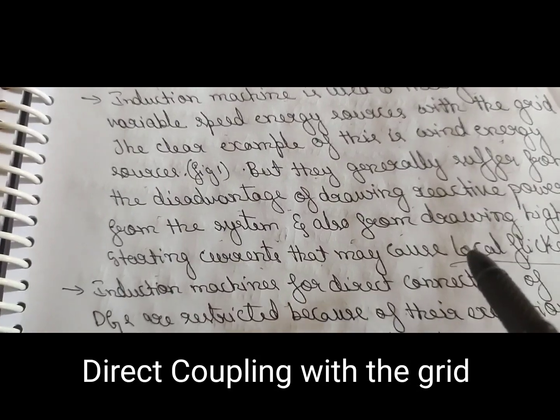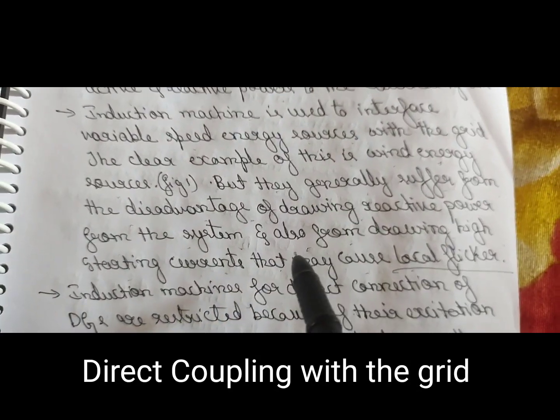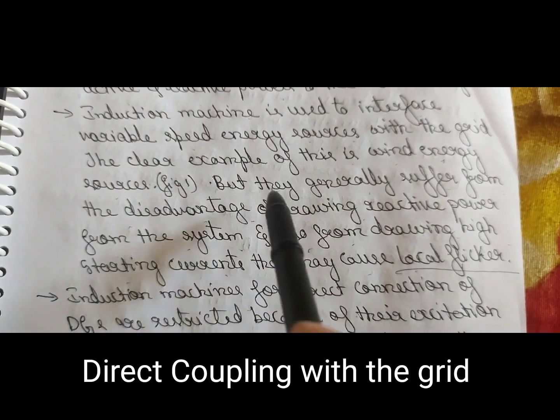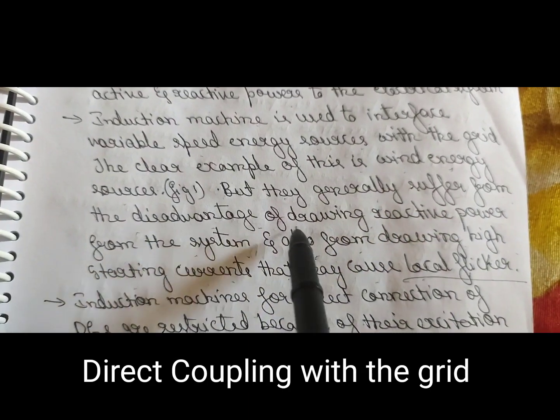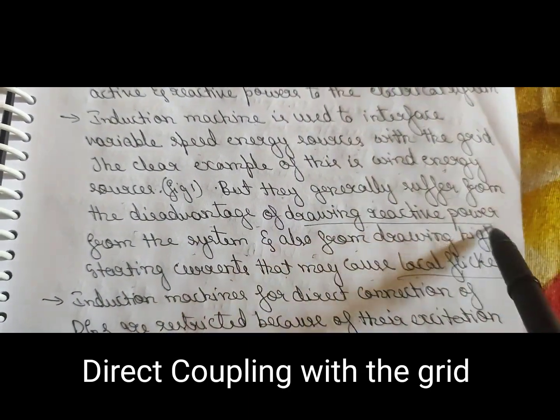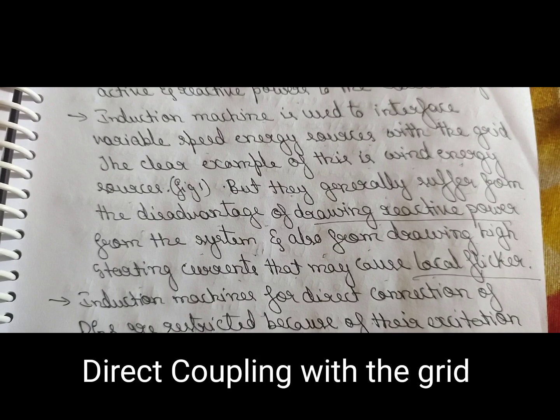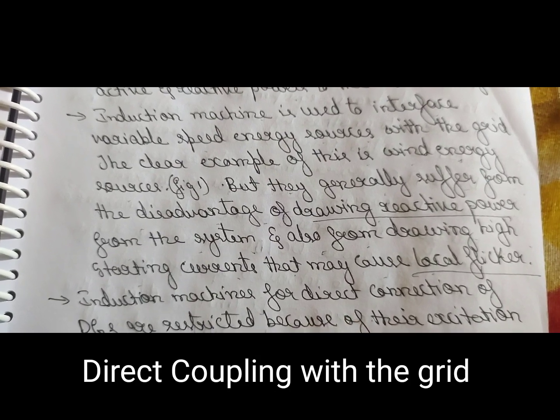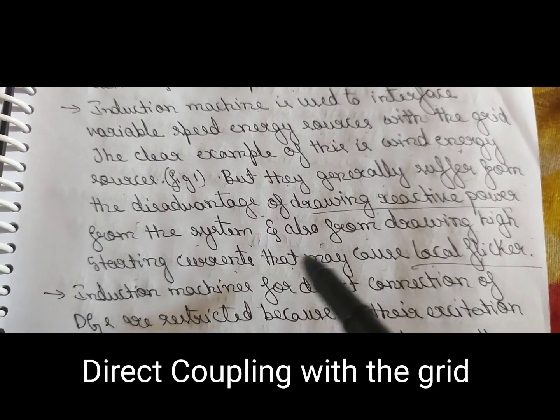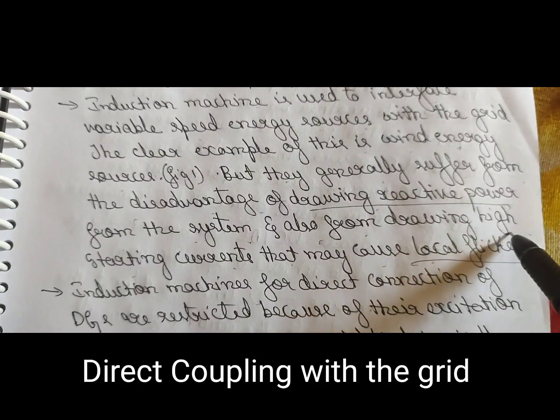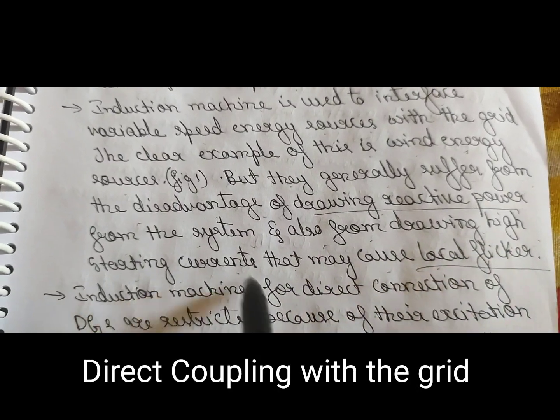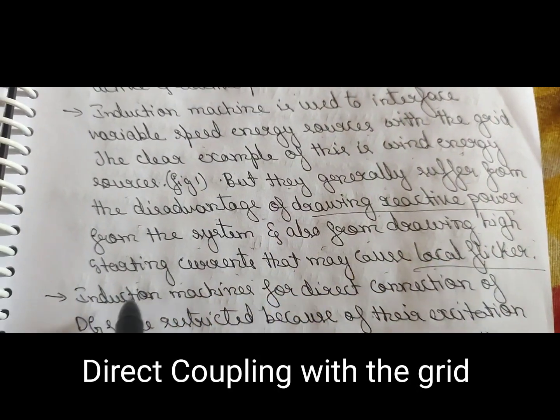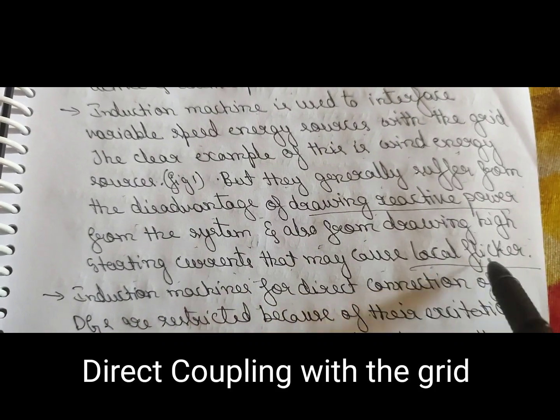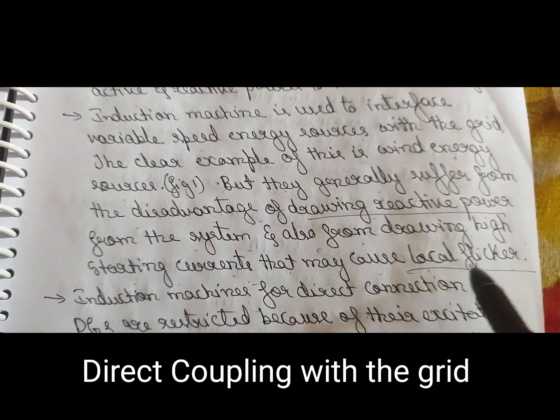So in the figure we have observed that we have used an induction generator. They generally suffer from the disadvantage that they draw reactive power. Induction generator means it will absorb reactive power from the system. It will also draw high starting currents that will cause a local flicker.